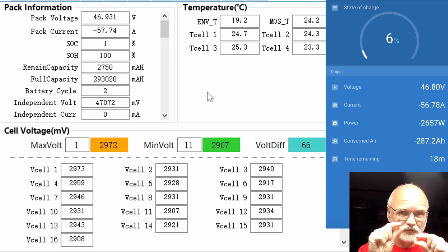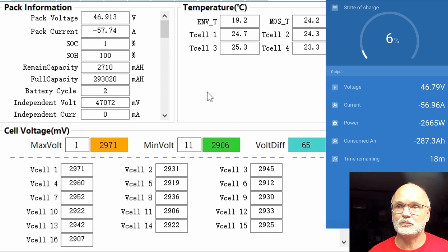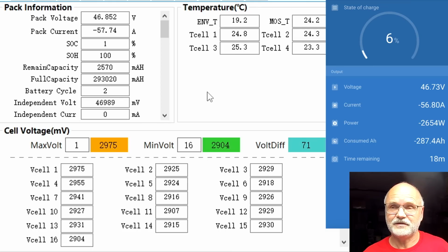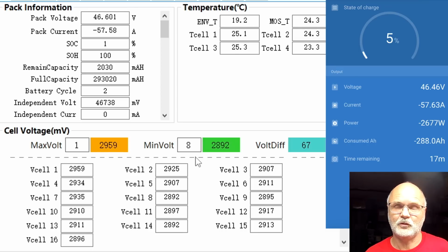But this is only a small variation the active balancer needs to balance then. 1%, the BMS claims. We did not come to 1% in the first discharge test with the active balancer active. At 3% there was nothing anymore. You can still see 9, 11, 14, several different cells are on a low voltage, which is fantastic. In the first test it was only cell number 5, which was always the lowest for quite a long time until the BMS shut off. But now it is changing all the time, which is perfect.